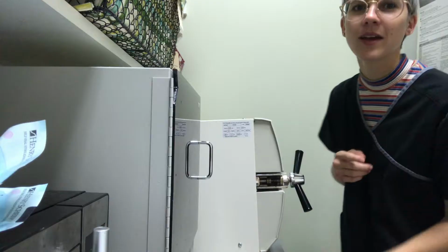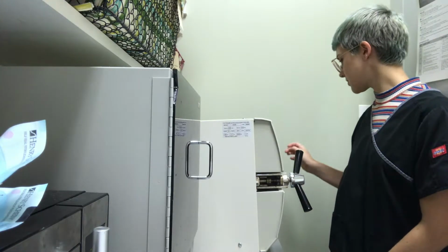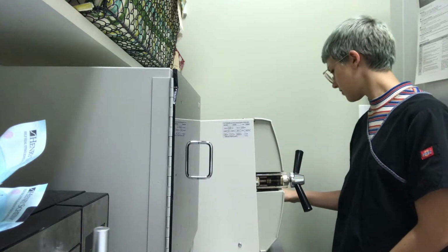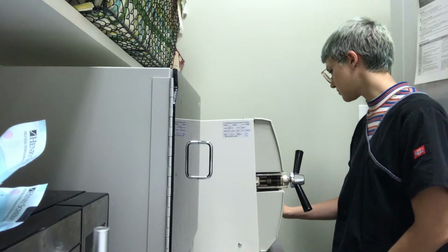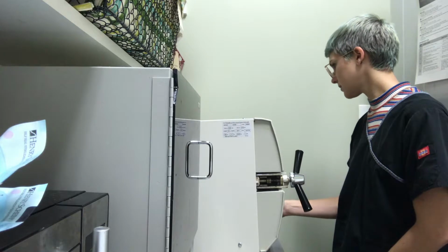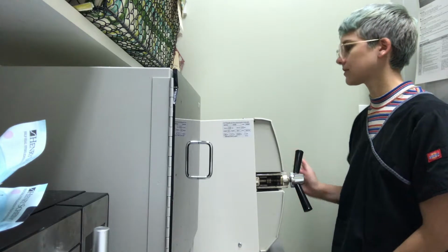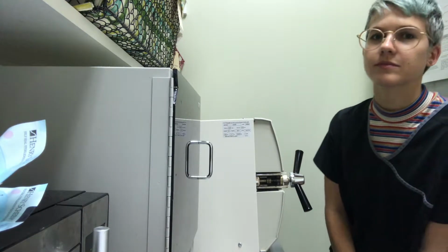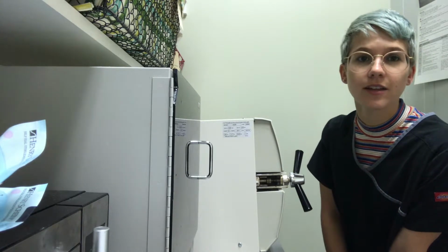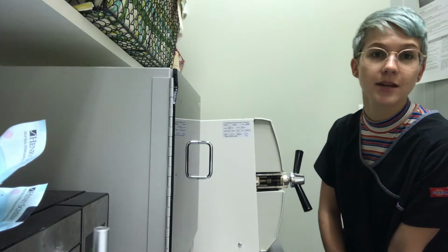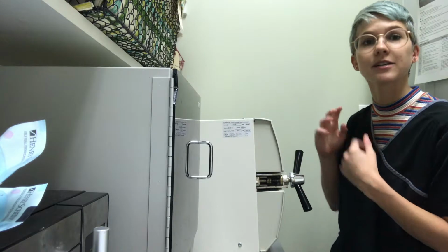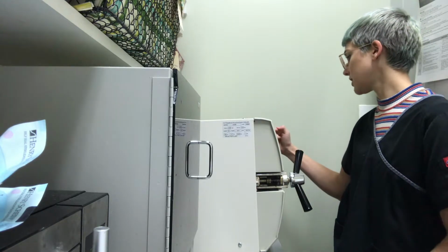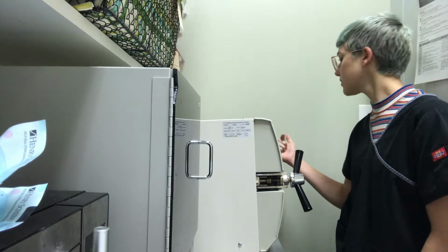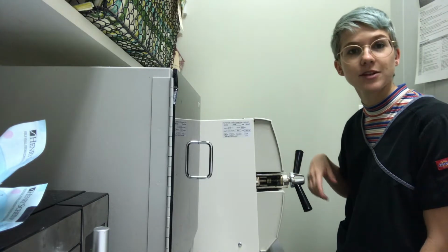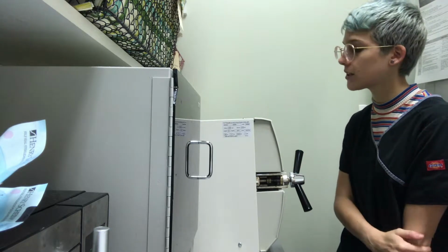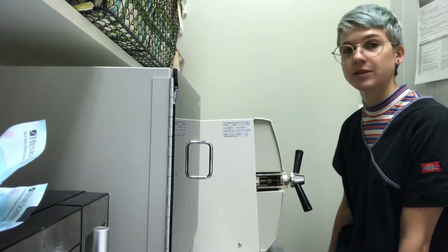Okay, so the timer for the autoclave just went off, so now I'm going to switch it over from sterilize to drain. So now it's draining all of the steam out, basically, that has built up pressure. And there's a pressure gauge here that I can watch go down. Once it's down to 0, then it is safe to open up the door. If I opened it before then, there would be too much pressure.